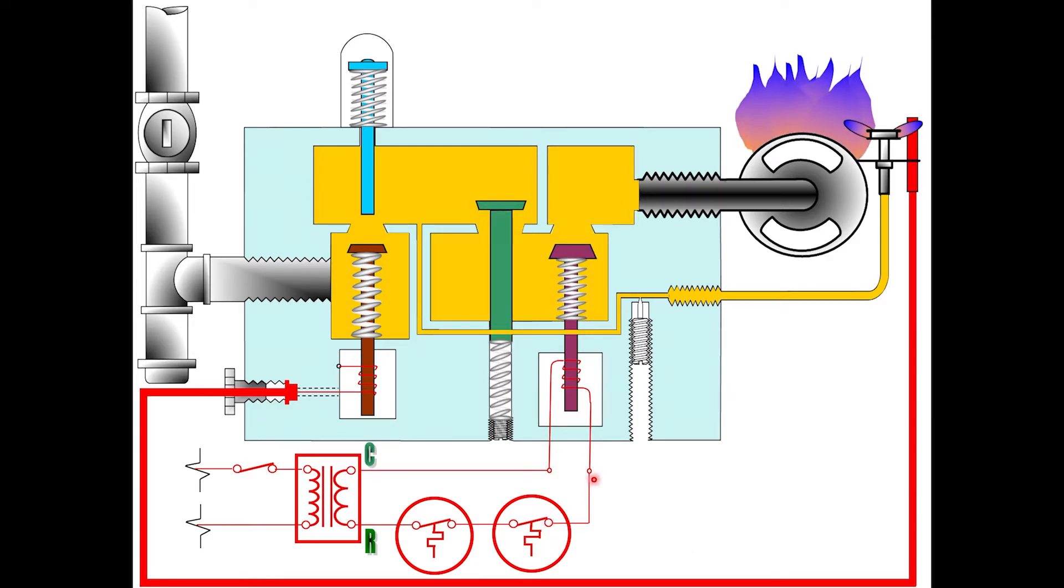So my switch closes, I get power to this. This is my solenoid portion of the gas valve. Now a solenoid just creates a small electromagnet which pulls a piece of metal down and in this case it's the actual solenoid valve that opened up to allow gas flow from the main chamber down through to the main burner.